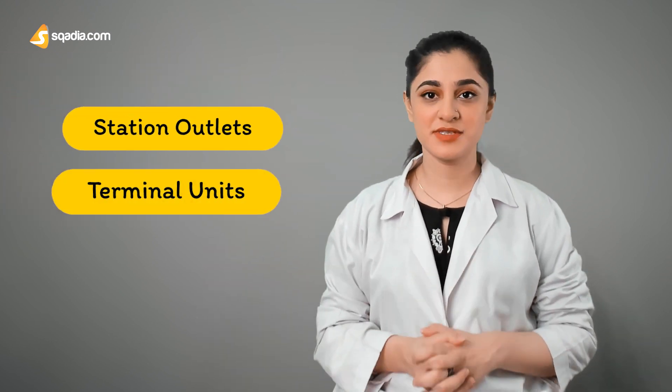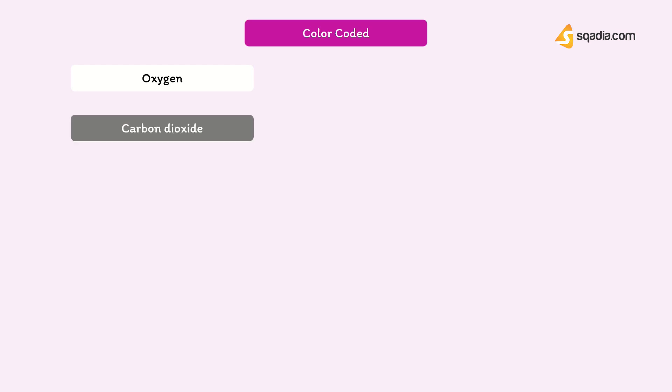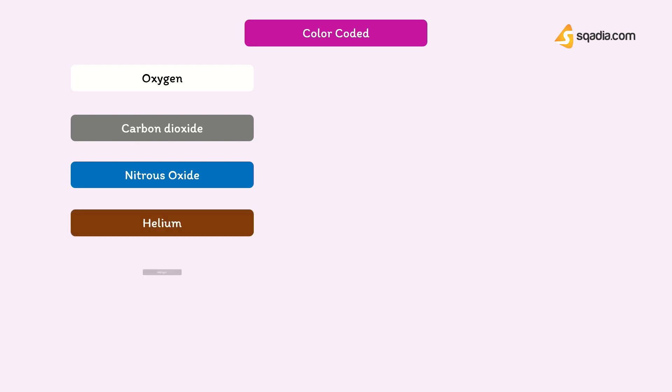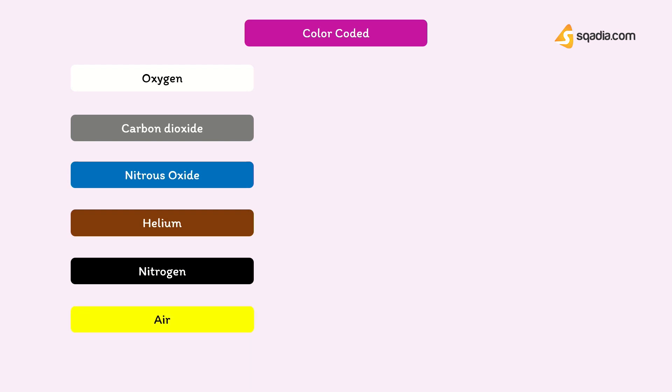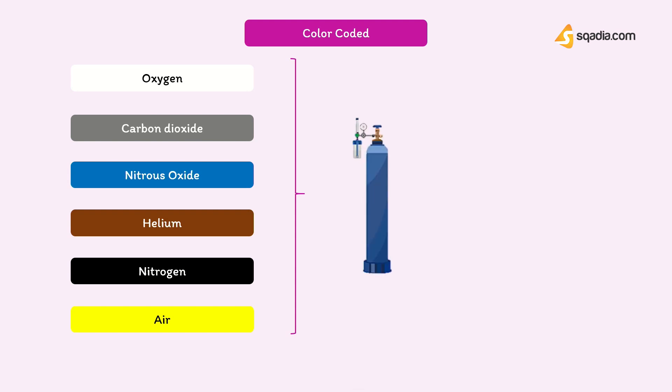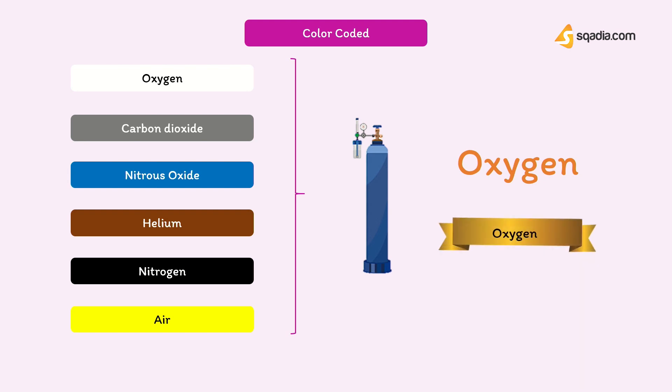Equipment is connected to the medical gas pipeline system through station outlets and terminal units. Medical gas systems are commonly color-coded to identify their contents: white for oxygen, gray for carbon dioxide, blue for nitrous oxide, brown for helium, black for nitrogen, and yellow for air. As coding systems and requirements vary by jurisdiction, the text or labeling is the most reliable guide to the contents.